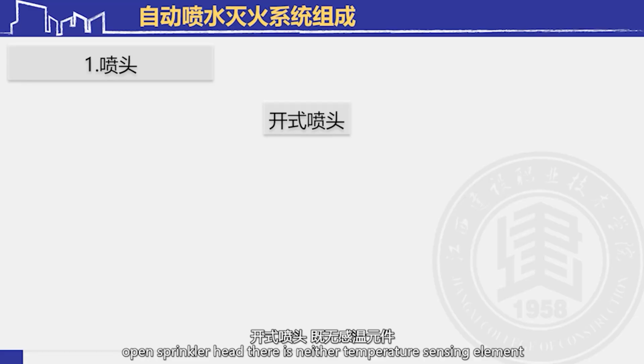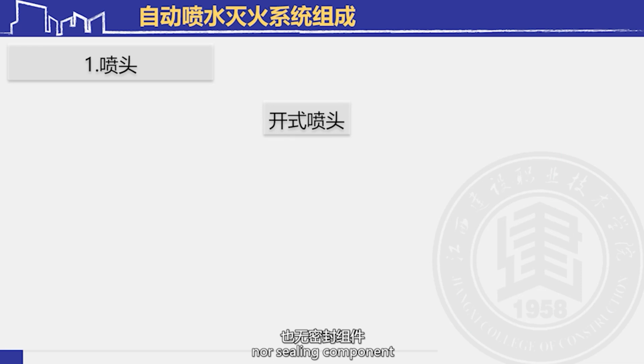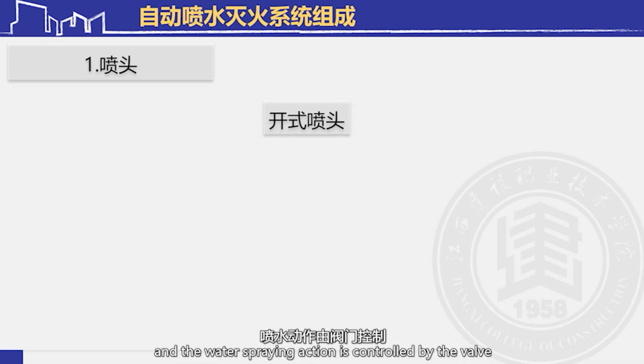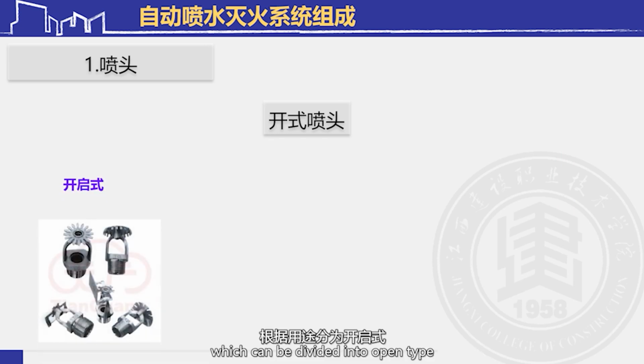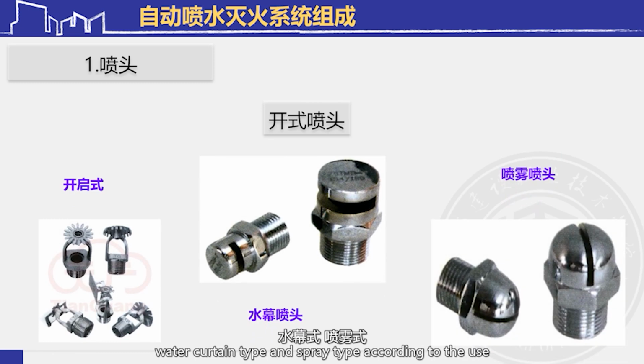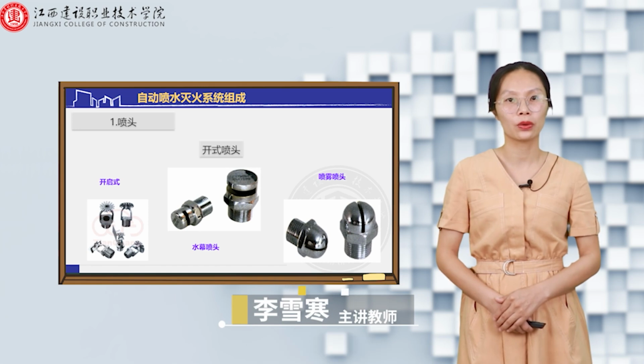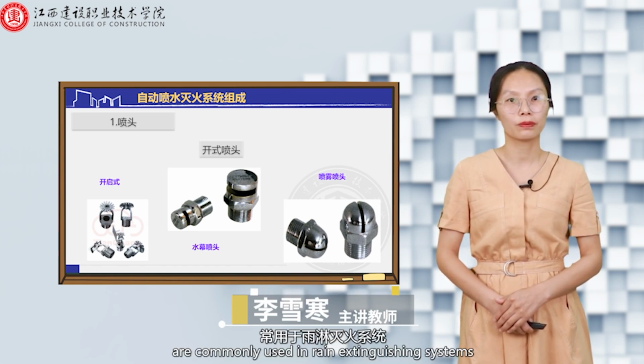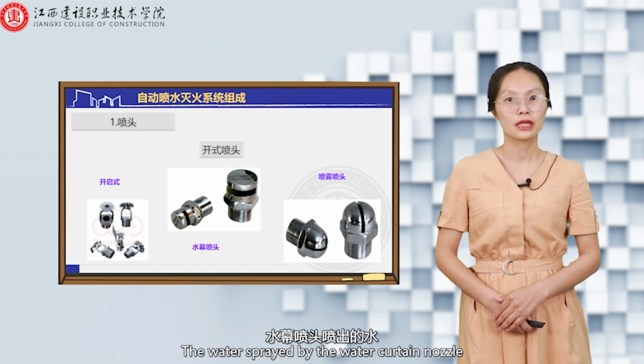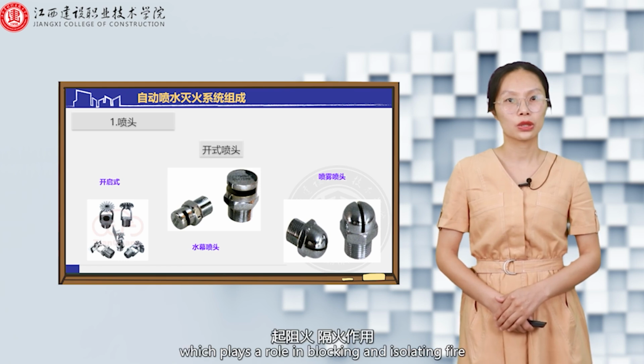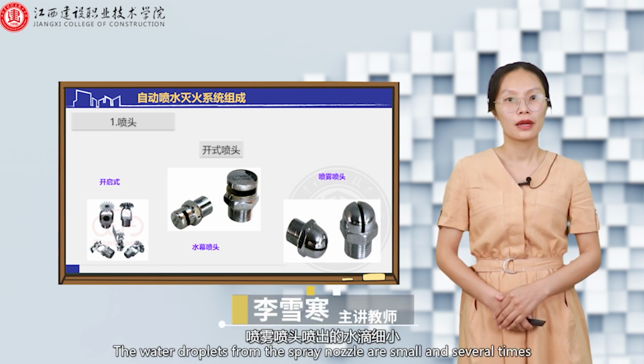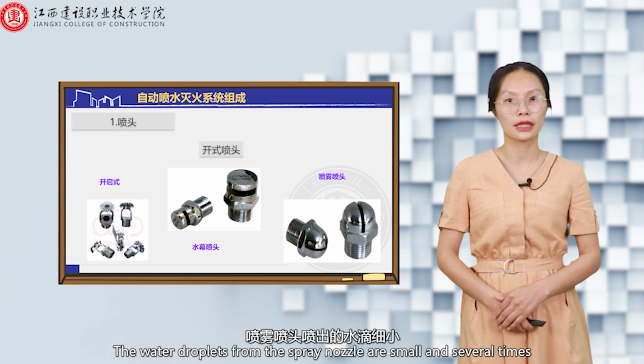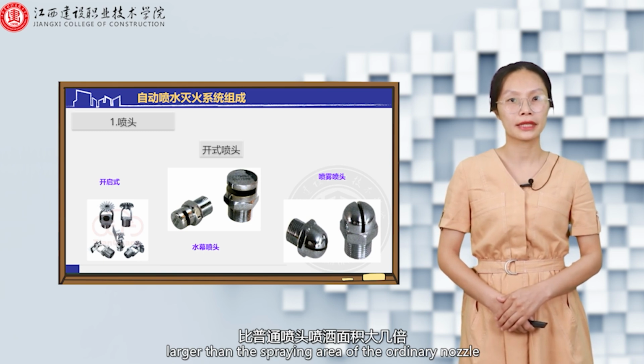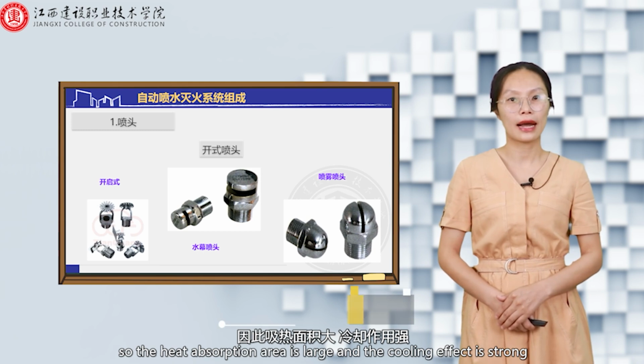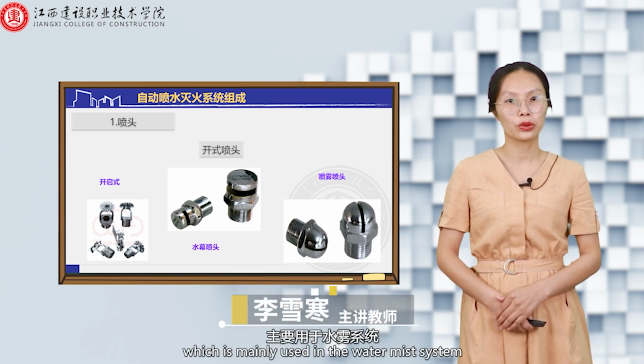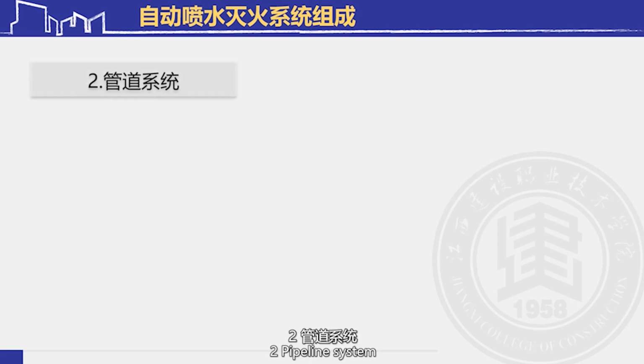Open sprinkler head has neither temperature sensing element nor sealing component, and the water spraying action is controlled by the valve, which can be divided into open type, water curtain type, and spray type according to the use. Open type sprinkler heads are commonly used in rain extinguishing systems. The water sprayed by the water curtain nozzle is in a uniform water curtain shape, which plays a role in blocking and isolating fire. The water droplets from the spray nozzle are small and the spraying area is several times larger than that of the ordinary nozzle, so the heat absorption area is large and the cooling effect is strong, which is mainly used in the water mist system. Second, pipeline system.